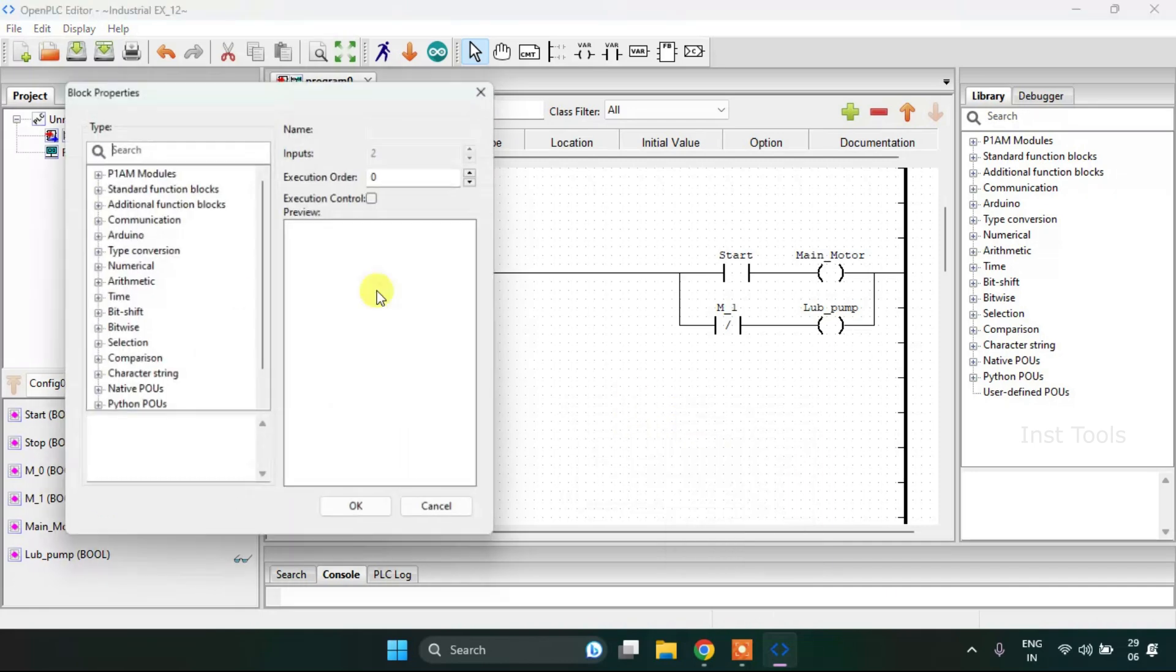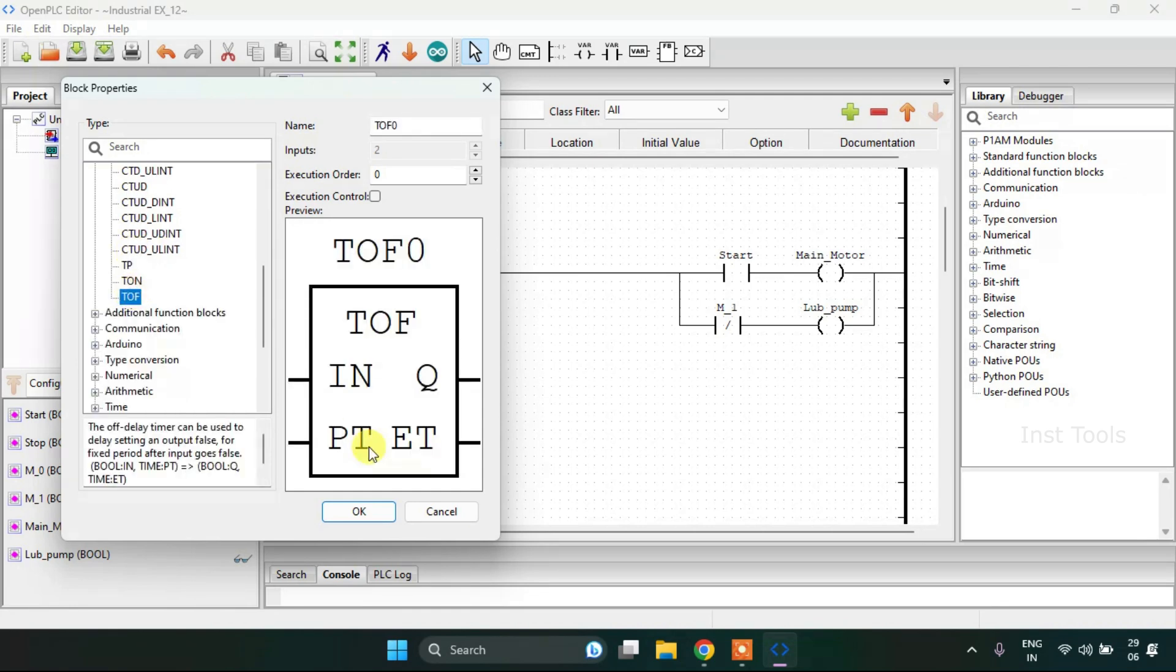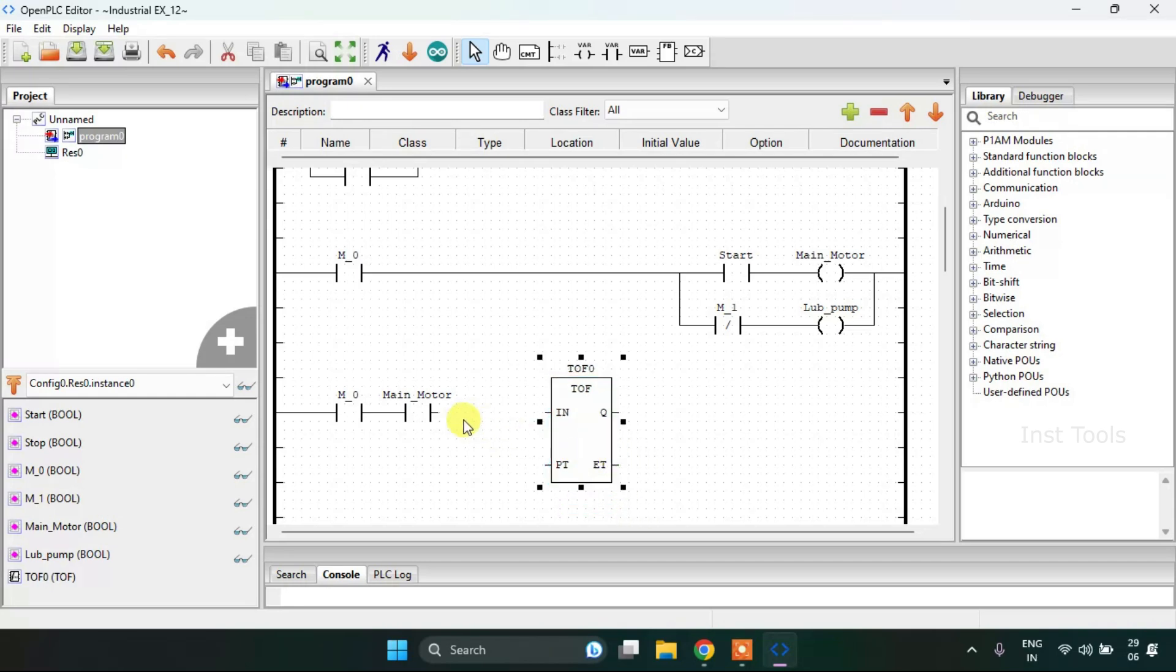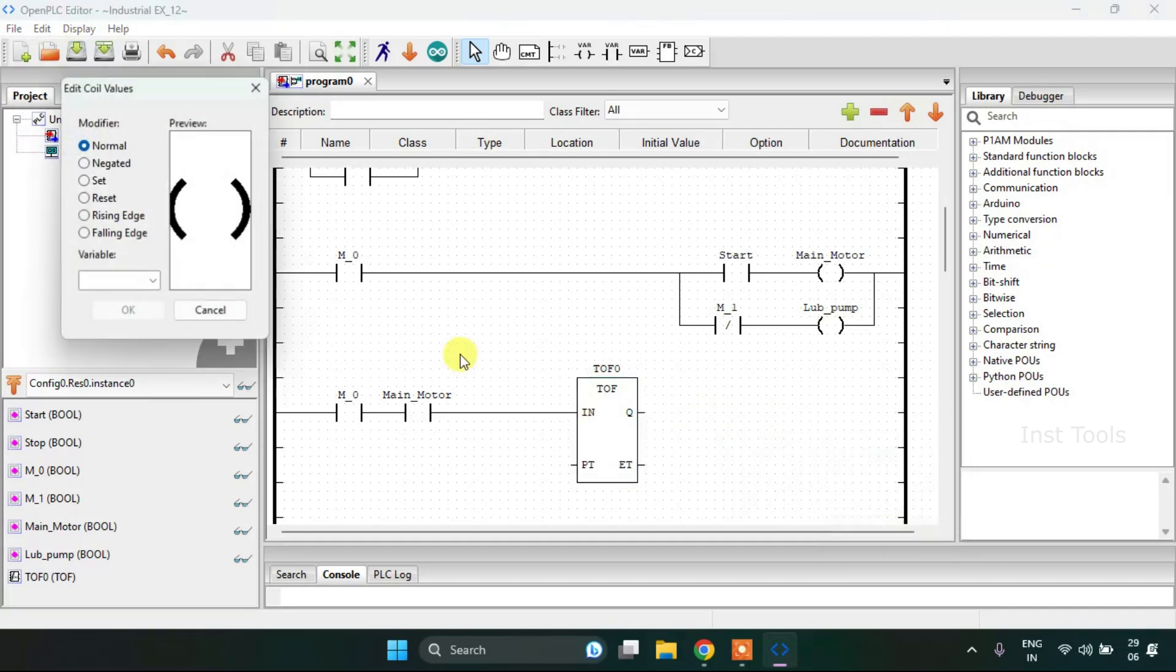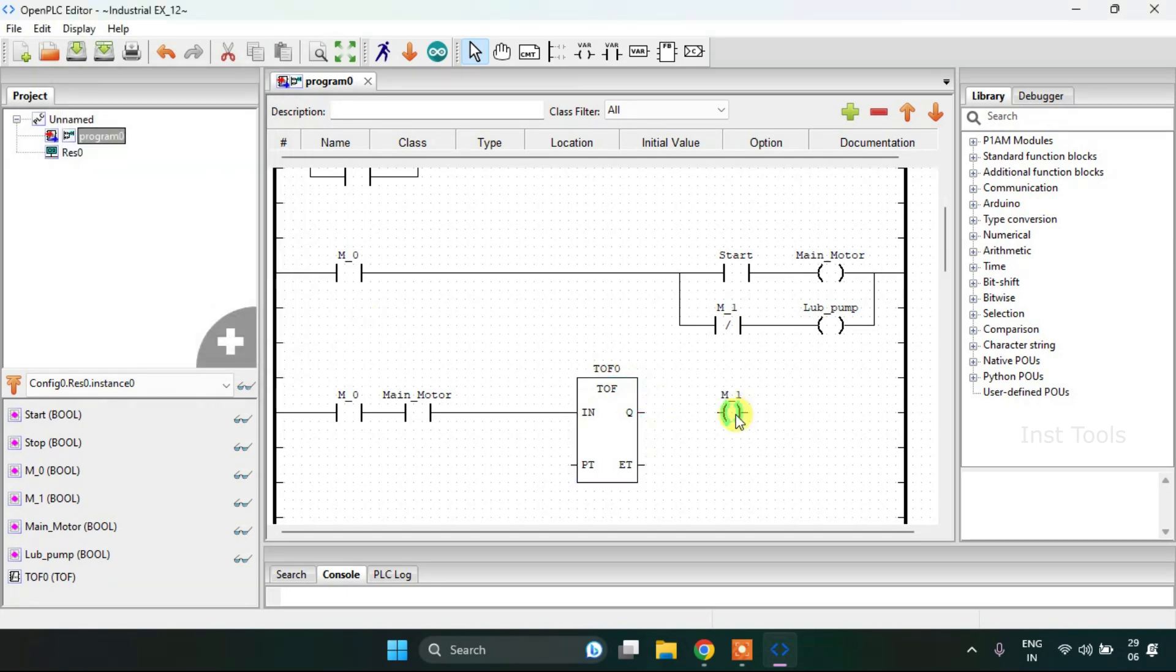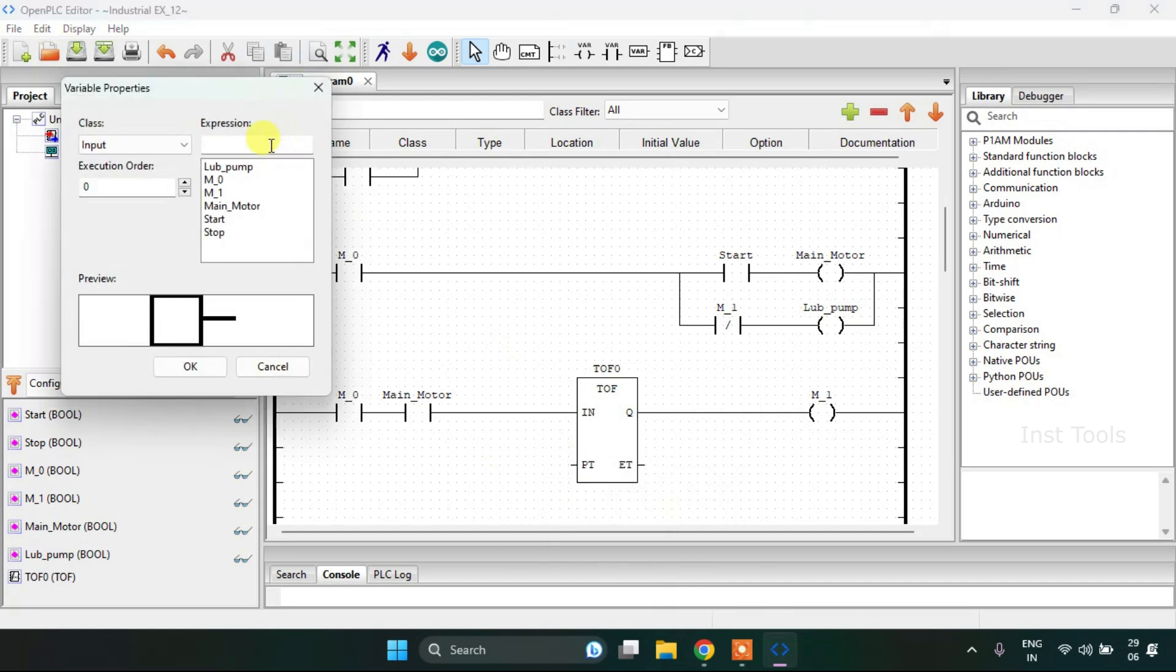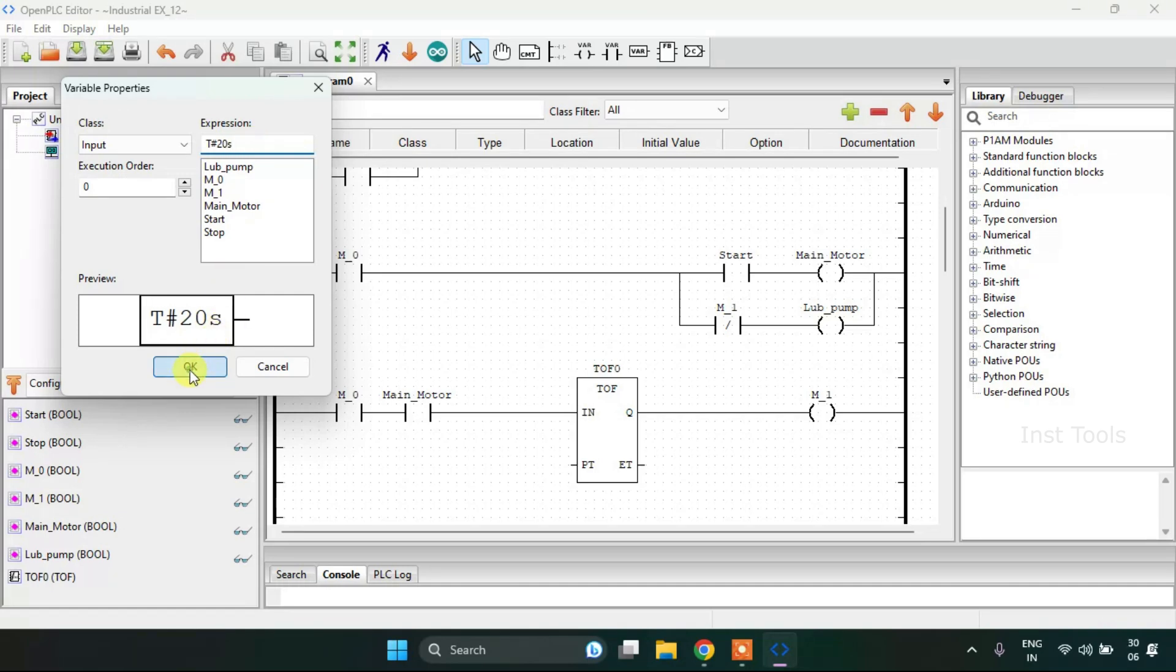Then I need a block from the standard function blocks which is going to be the TOF. I'll increase the size, then I will connect the pins and add a coil. Now I'm going to join these pins, and lastly I need to add a variable for 20 seconds which is the preset time.